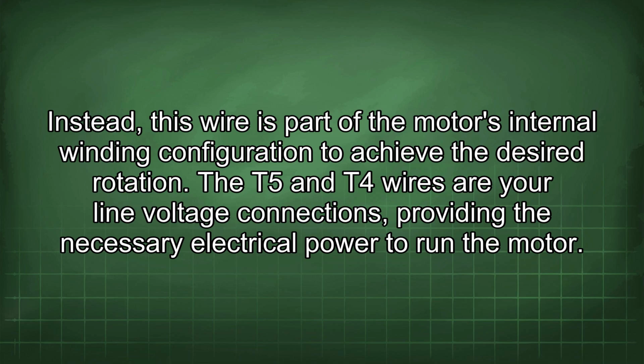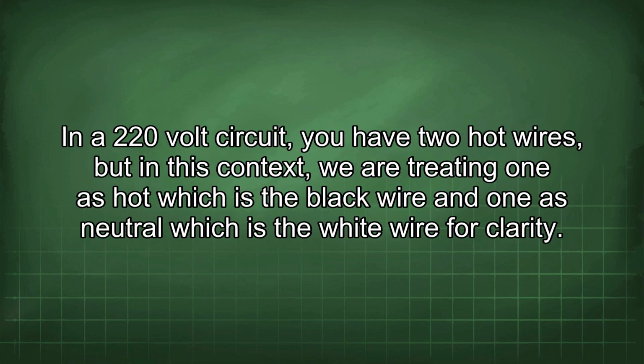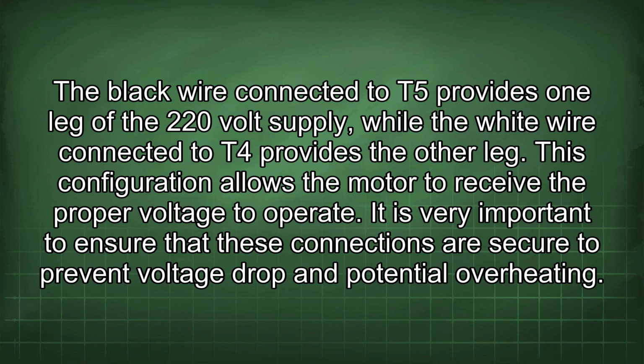The T5 and T4 wires are your line voltage connections, providing the necessary electrical power to run the motor. In a 220-volt circuit, you have 2 hot wires, but in this context, we are treating one as hot, which is the black wire, and one as neutral, which is the white wire, for clarity. The black wire connected to T5 provides one leg of the 220-volt supply, while the white wire connected to T4 provides the other leg. This configuration allows the motor to receive the proper voltage to operate. It is very important to ensure that these connections are secure to prevent voltage drop and potential overheating.